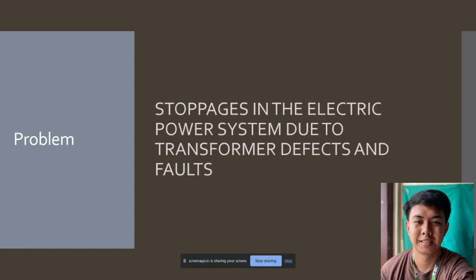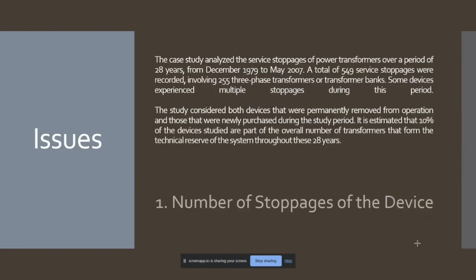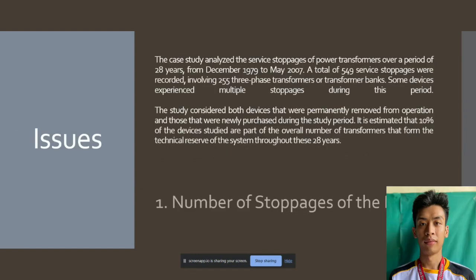Problems: stoppage in the electric power system due to transformer defects and faults. Issues. The case study analyzed the service stoppages of power transformers over a period of 28 years, from December 1979 to May 2007. A total of 549 service stoppages were recorded, involving 255 three-phase transformers or transformer banks. Some devices experienced multiple stoppages during this period.